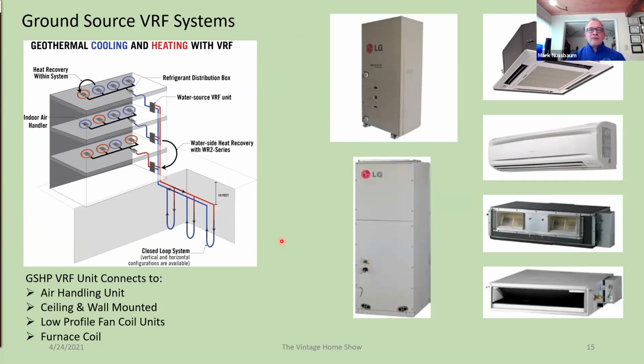So again, it really depends on the manufacturer, and not all manufacturers have a water-cooled single phase version of this. You need single phase electric because that's what residential buildings have. They make these in 3-phase, but the single phase is what we need. So there's a couple of manufacturers that have them. I think more are coming on. Five years ago you couldn't get them, but now there are other ones that are having them. So it makes it a very versatile installation type.